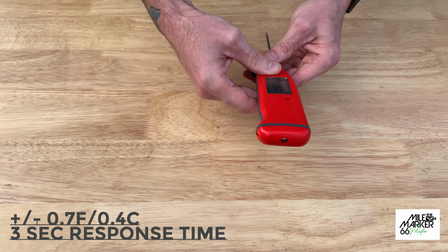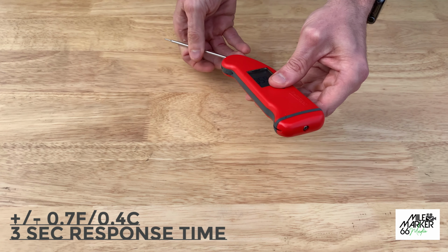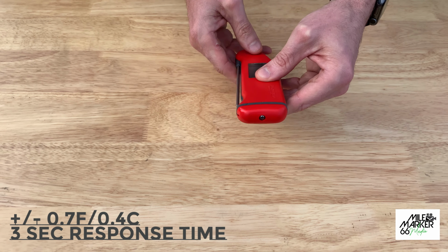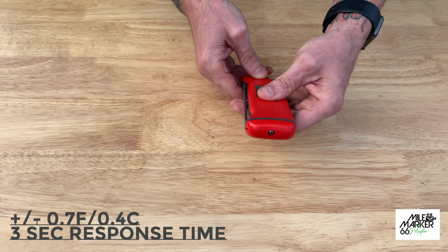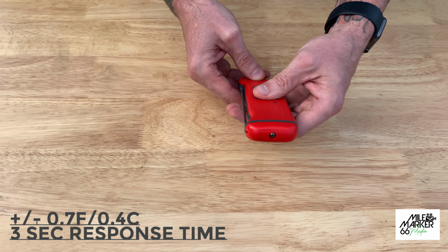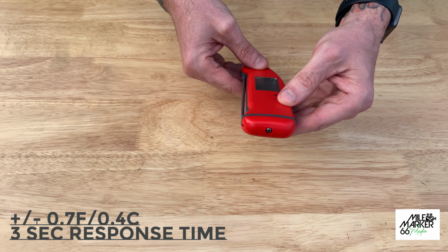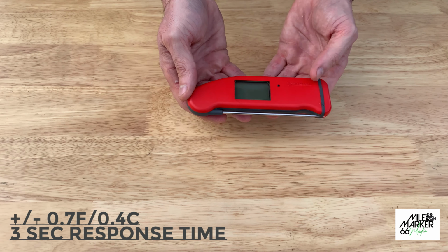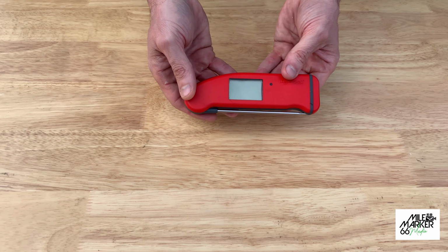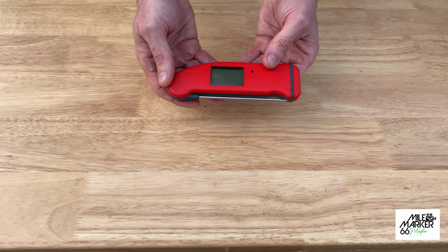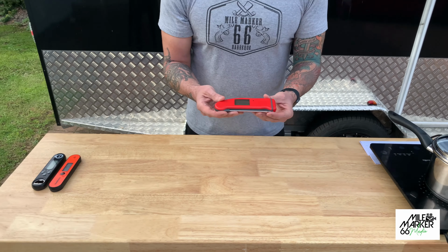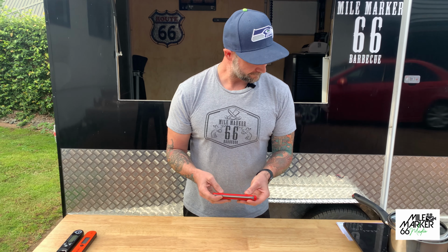This has a manufacturer's advertised response time of 3 seconds, and it's got an accuracy of plus or minus 0.7 degrees Fahrenheit or plus or minus 4 degrees Celsius, so quite accurate. Now, while you can validate the accuracy of this probe, you can't calibrate it at home. If you feel that it is reading out and you want to calibrate it, it's got to go back to the factory, so it's only factory calibrated.